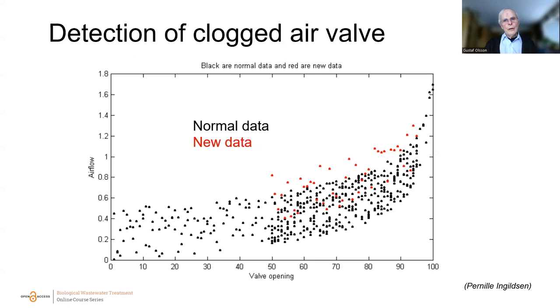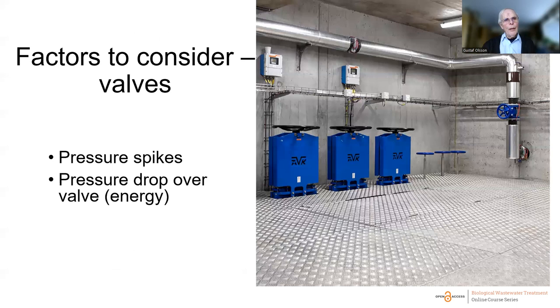We can actually observe valve behavior as part of monitoring. For an air valve, the black dots show the relationship between airflow and valve opening at one point in time. The red dots, taken at a later occasion, show a different airflow behavior — indicating something abnormal in the valve. By measuring airflow and valve opening together, we can detect the valve's behavior, essentially monitoring equipment to ensure it is operating properly.